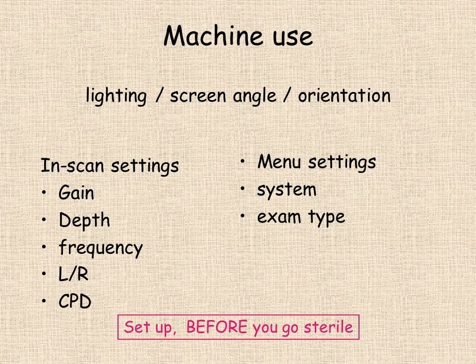And the kind of things you should set up before you go sterile are in scan settings, the gain, the depth, the frequency. And don't forget that the screen has a button that reverses left and right, and if that's been reversed on you without you realizing it, it could cause a problem.